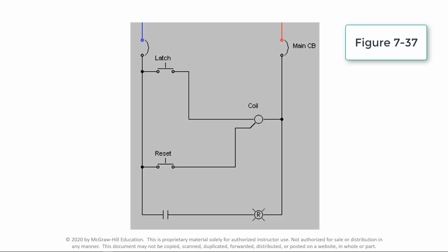Note that the latch relay coil does not have to be continuously energized to hold the contacts closed and keep the light on. The only way to switch the lamp off is to actuate the reset button, which will energize the unlatched coil and return the coil contact to its open, unlatched state. In cases of power loss, the relay will remain in its original latched or unlatched state when power is restored.